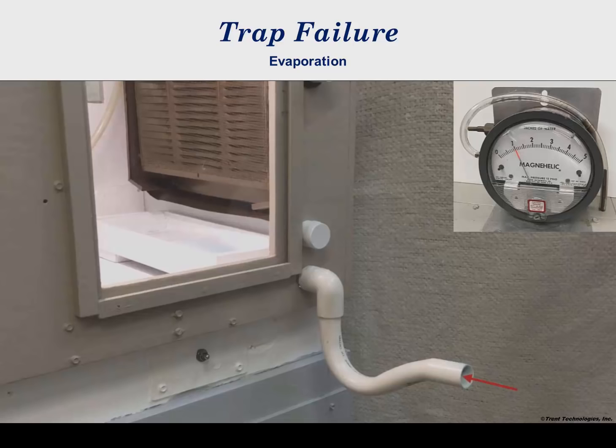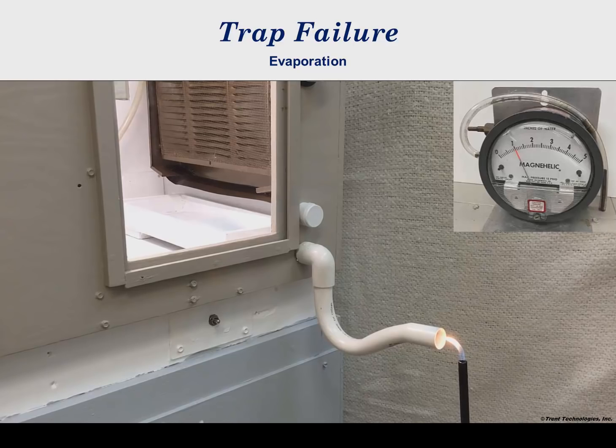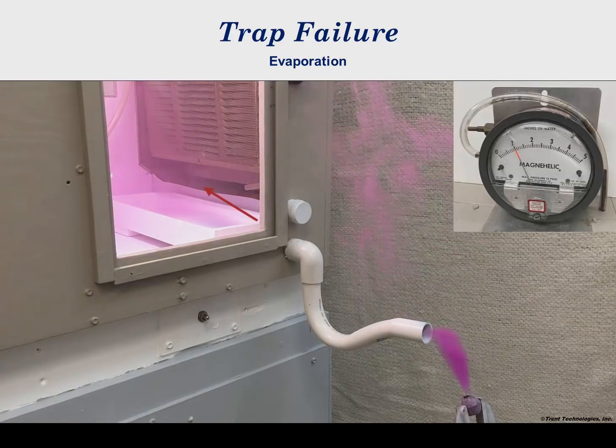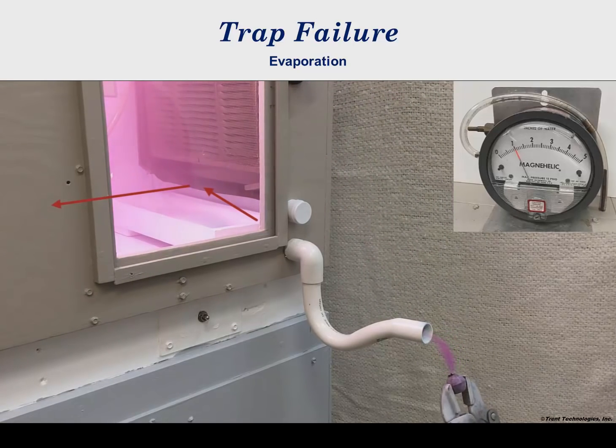During startup after a heating cycle, like for summer cooling, trap water is evaporated, allowing air ingestion. Deflection of the butane lighter flame shows how contaminated air can be drawn into the unit, and the introduction of smoke near the drain outlet shows how polluted air can be drawn into the system and spread into the conditioned space.